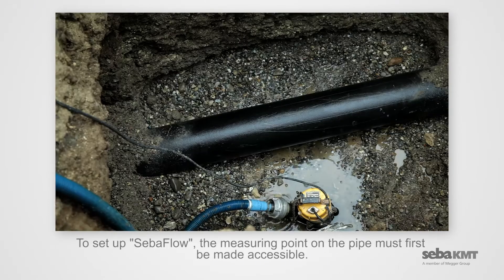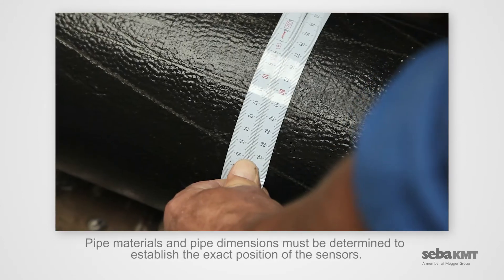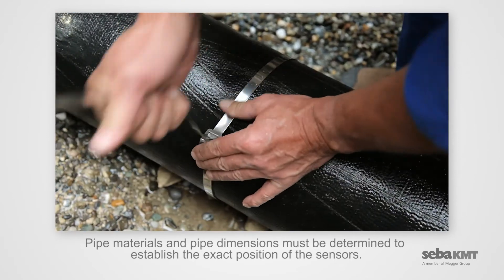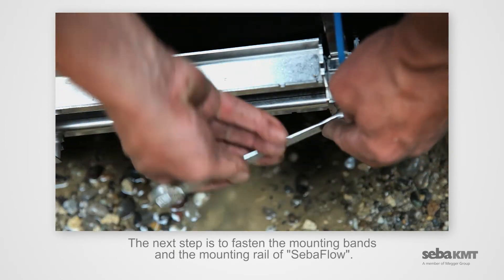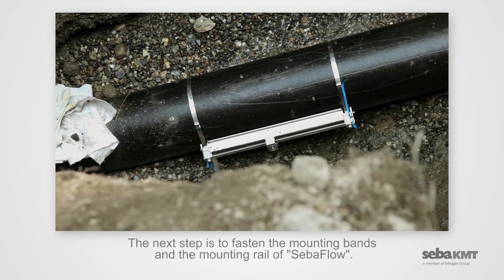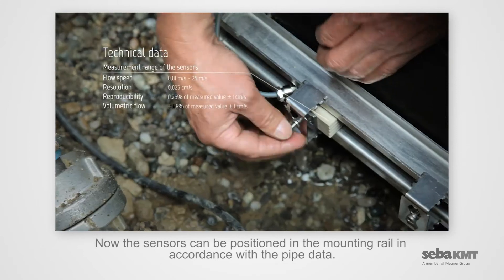To set up SebaFlow, the measuring point on the pipe must first be made accessible. Pipe materials and pipe dimensions must be determined to establish the exact position of the sensors. The next step is to fasten the mounting bands and the mounting rail of SebaFlow. Now the sensors can be positioned in the mounting rail in accordance with the pipe data.